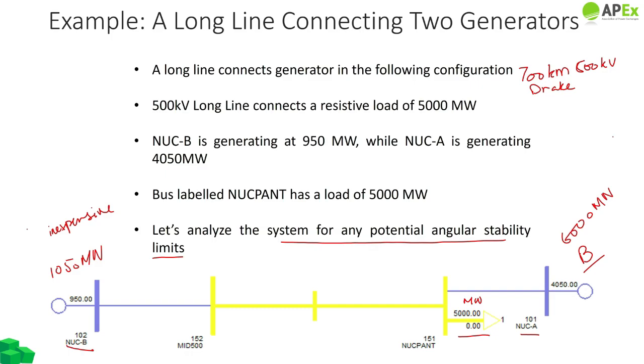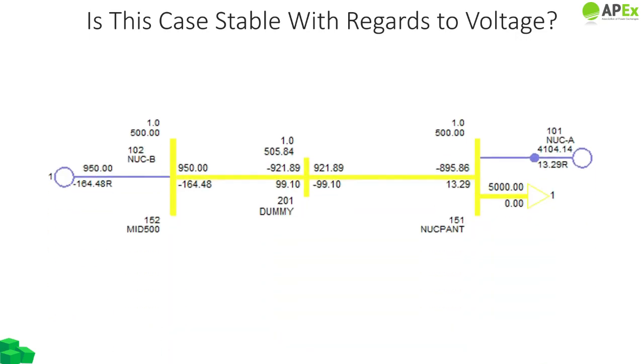So after simulating this system, firstly we will see if there is an issue with regards to voltage stability. Here are the results of the load flow. Our inexpensive generator, generator B, is producing 950 megawatts. However, while reaching the load through our very long transmission line, we are only receiving 895 megawatts. Okay, while our slightly expensive generator, generator A, is producing 4104 megawatts to supply this load.